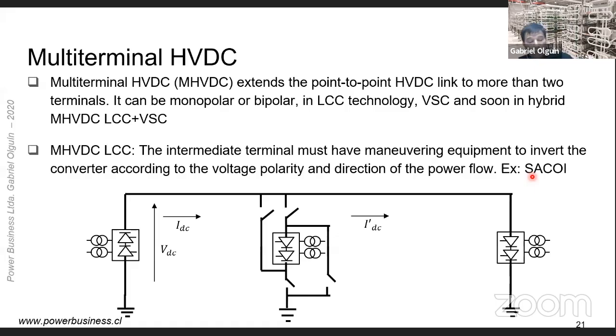Most common HVDC links are point-to-point or two-terminal links. It is, however, possible to build HVDC links with more than two terminals. Multi-terminal HVDC can be monopolar or bipolar. They can use LCC or VSC technology. And China is currently commissioning a hybrid multi-terminal HVDC that combines LCC and VSC converters. LCC multi-terminal HVDC requires that the intermediate terminal be equipped with maneuvering equipment to reverse energize the converter according to the voltage polarity and the direction of power in the main converters.